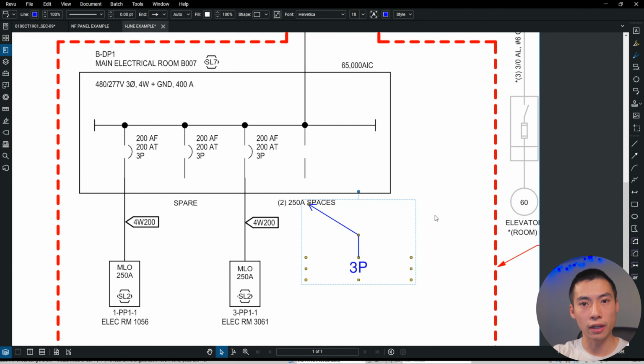Specifying the space makes sure that the contractor doesn't try to not order that. There is an 18-inch available, but I wanted the 22.5. So if I specify the spaces, they'll understand that we need that, so please don't order a smaller one. Okay, well, anyways, hopefully that helps somebody and avoids a change order. So pay attention to the fact that you have different panel types and you have to show them all differently.